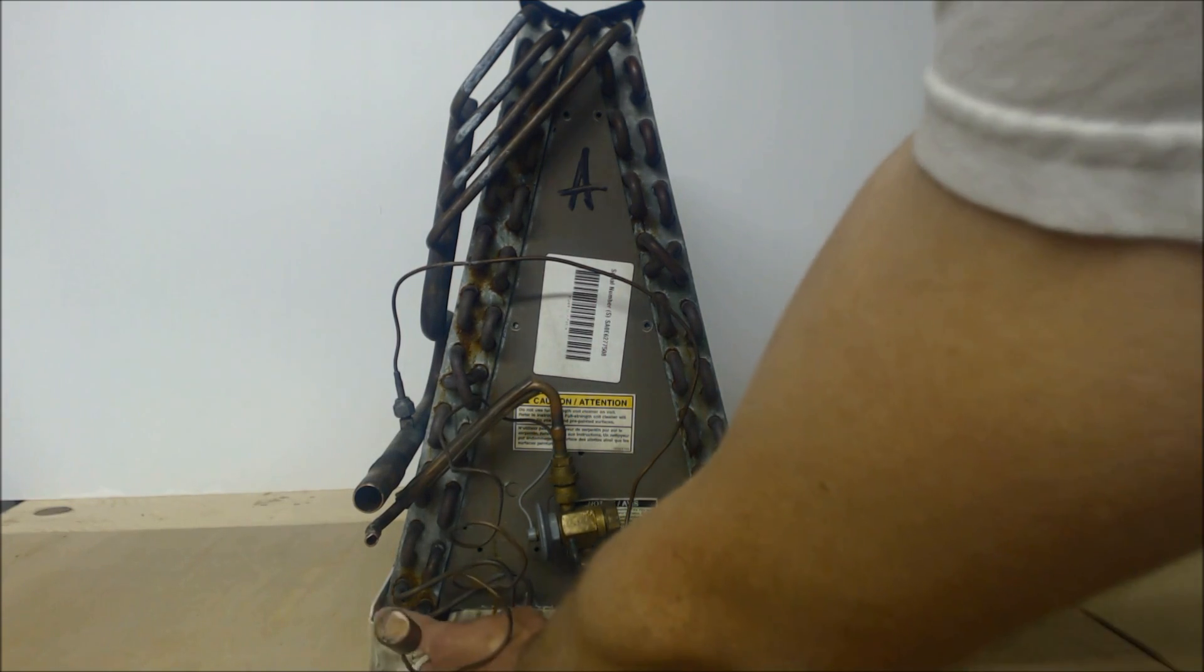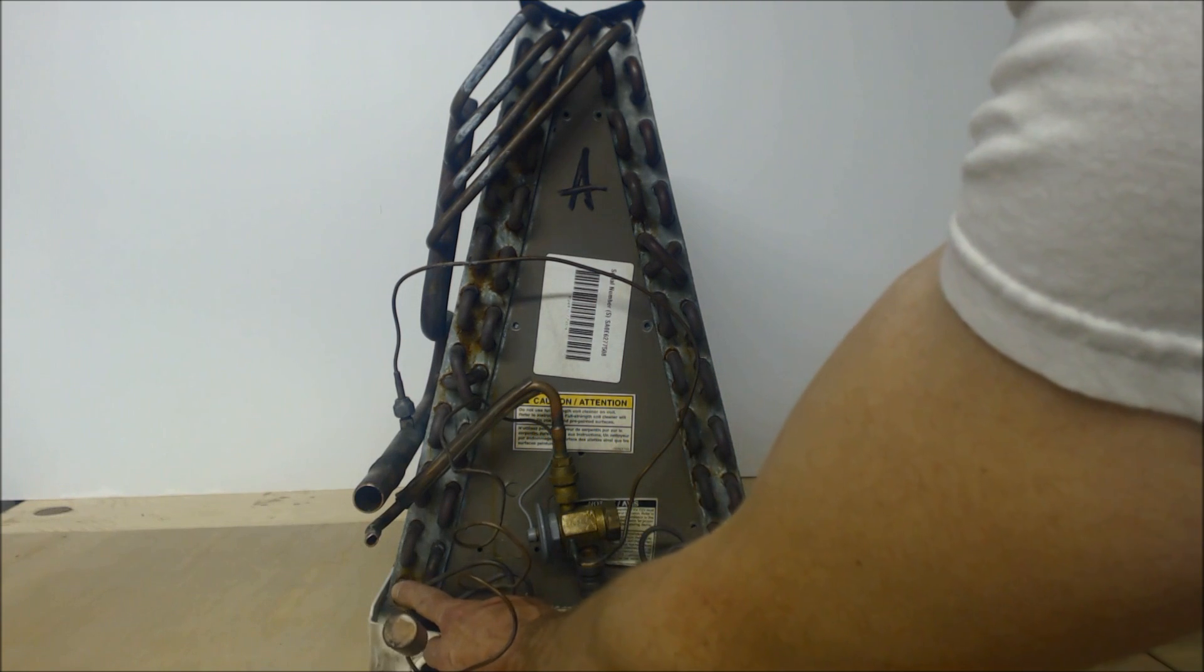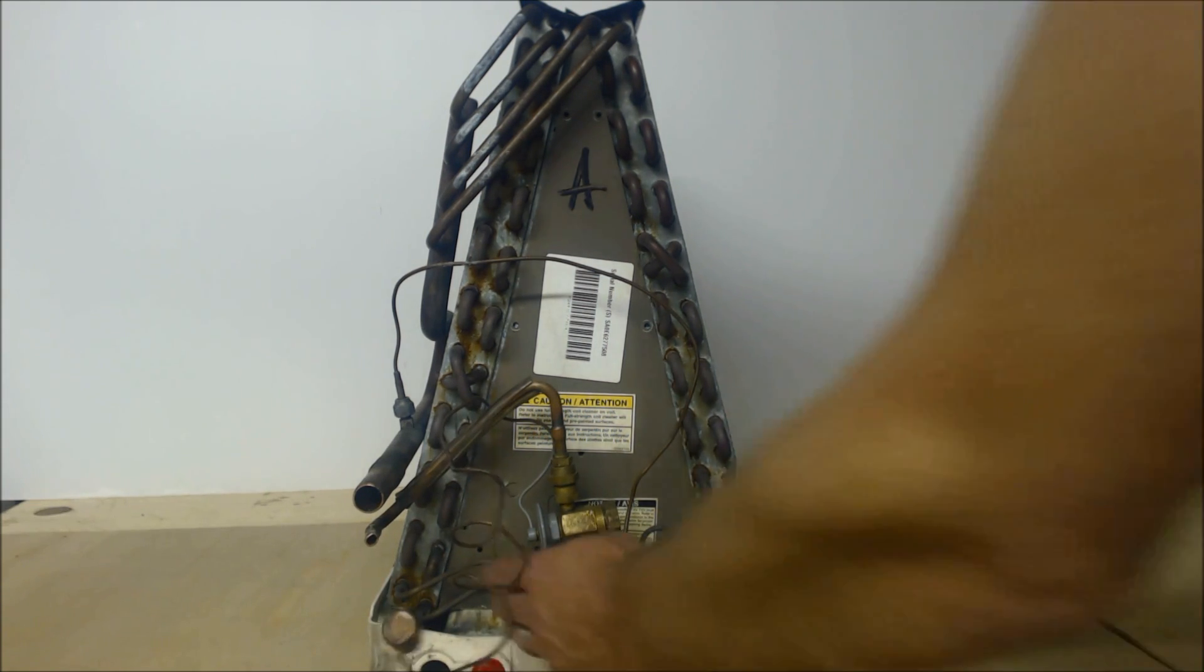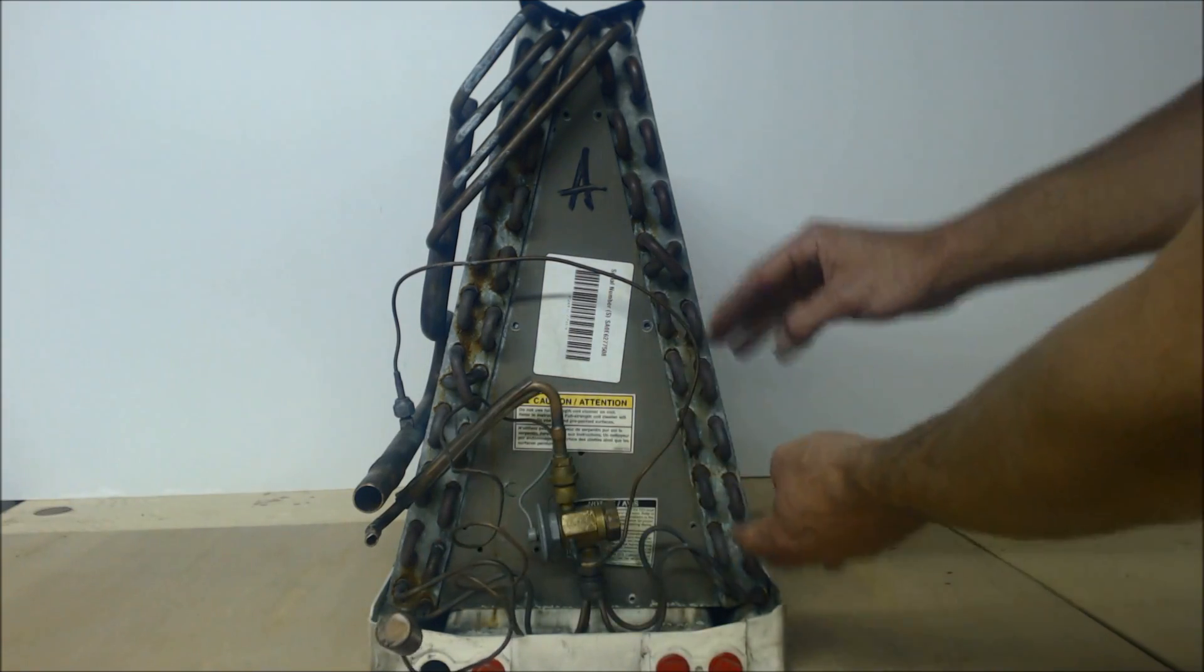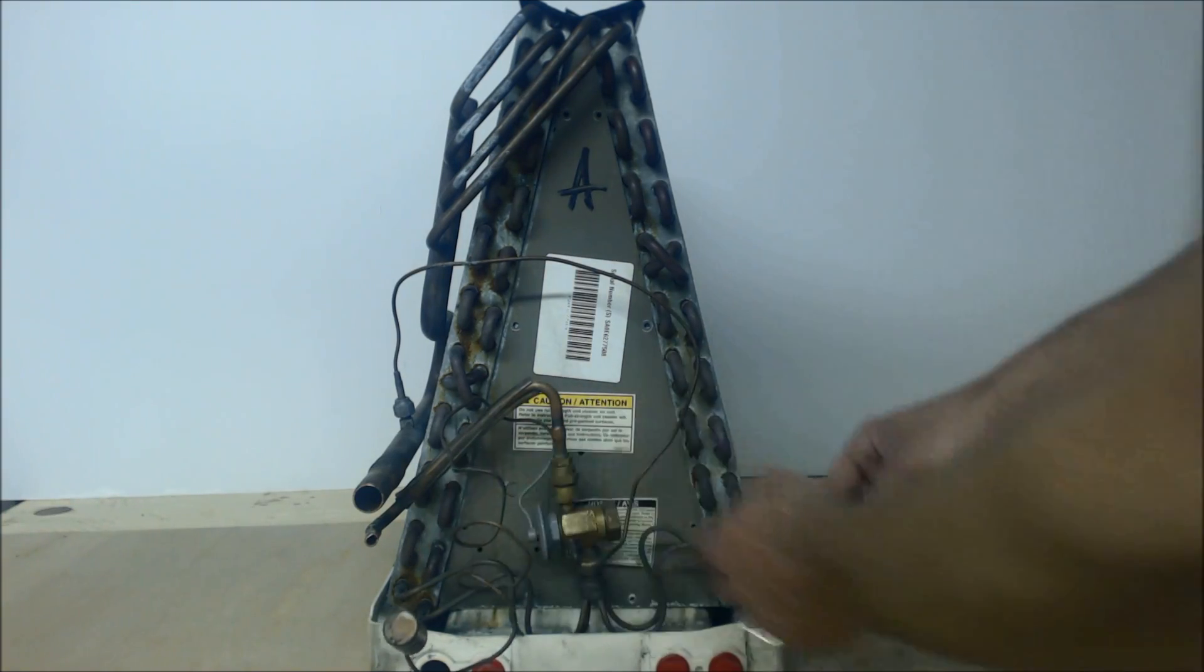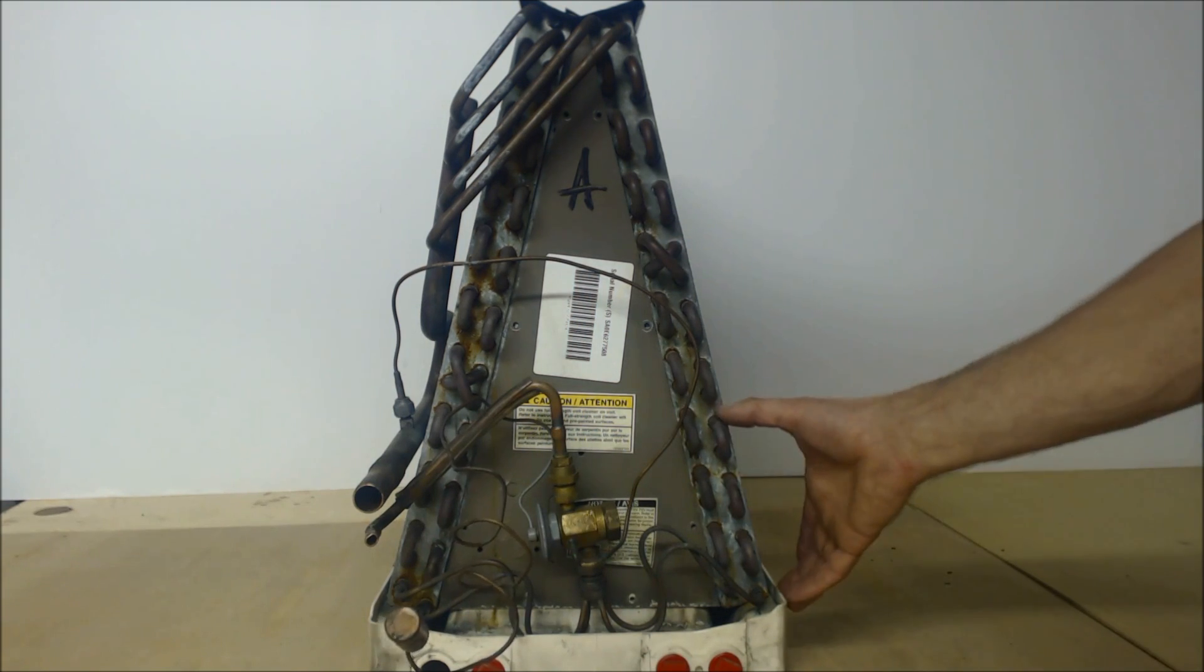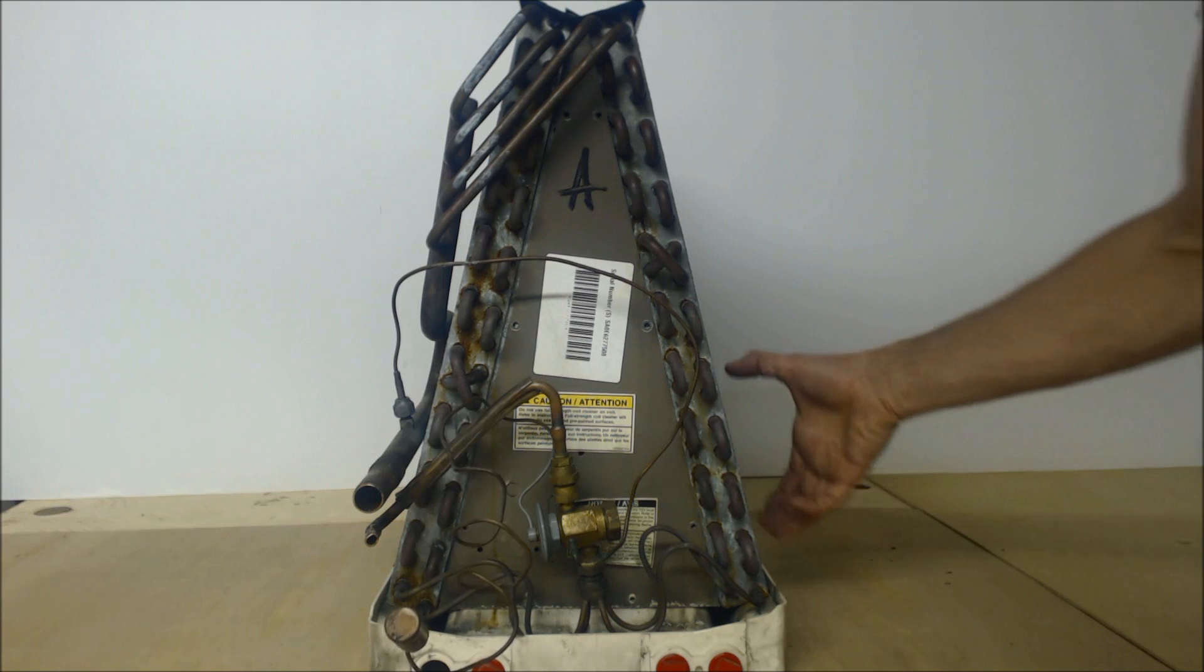Then it comes into the bottom of the evaporator coil as 20% flash gas and 80% liquid, and comes up to the midpoint. All that time it's absorbing heat. The bottom part is mainly liquid.